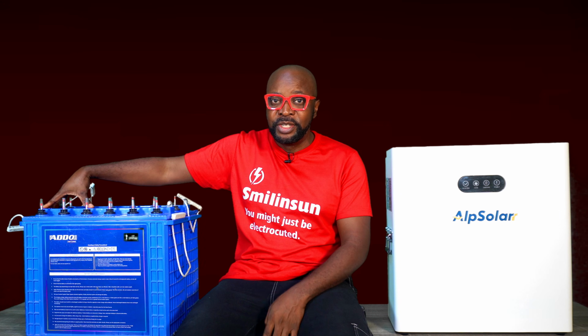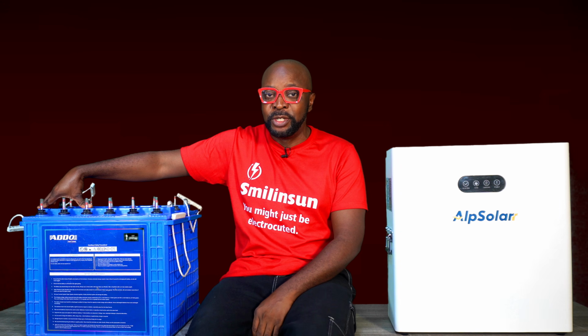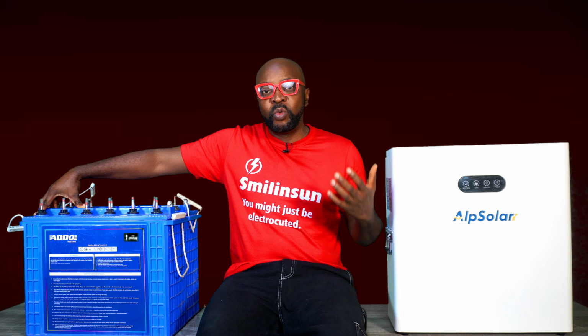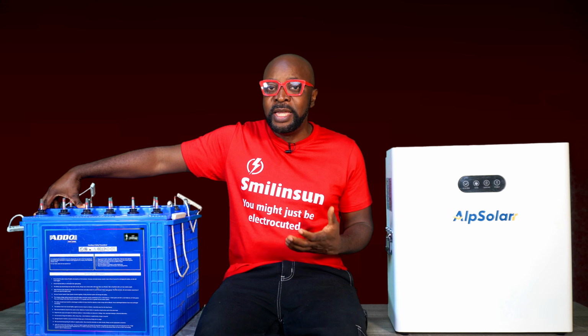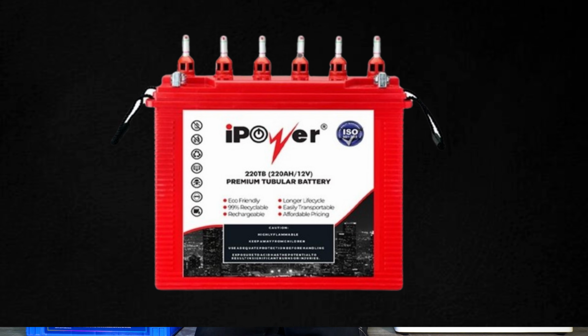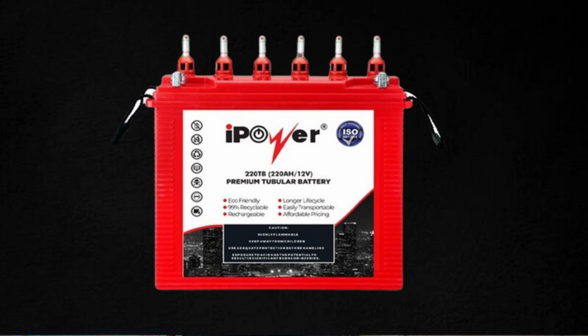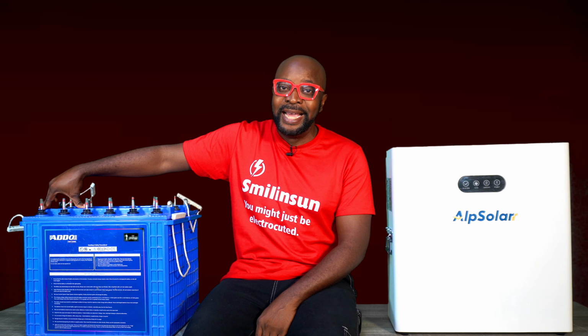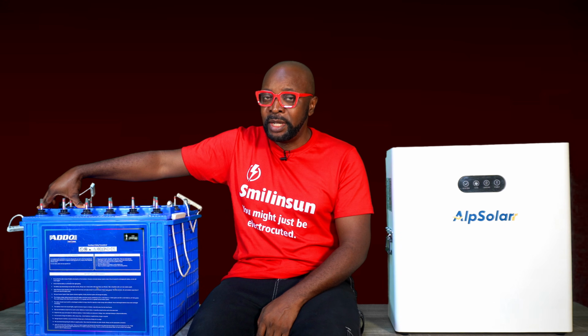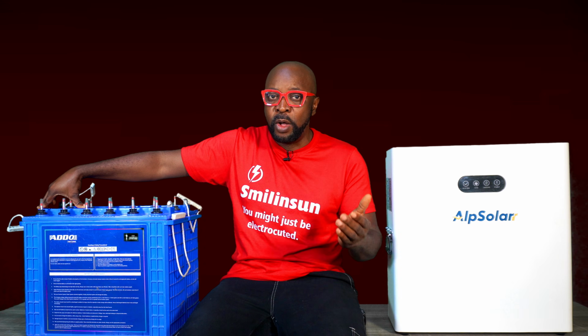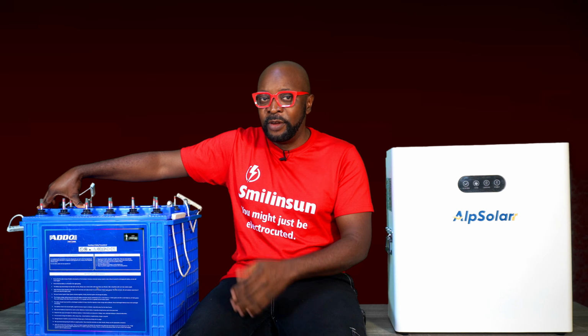The tubular battery does not support fast charging, due to some chemical limitations. You have a lot of chemical reactions when you try to charge the battery very fast. The batteries tend to overheat, and when they overheat, you lose a lot of energy in the process. So it's said to be around 70 to 80% energy efficient. It's typically charged in 3 stages: bulk, absorption, and then float.